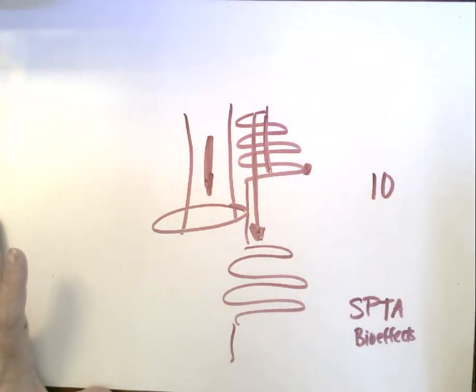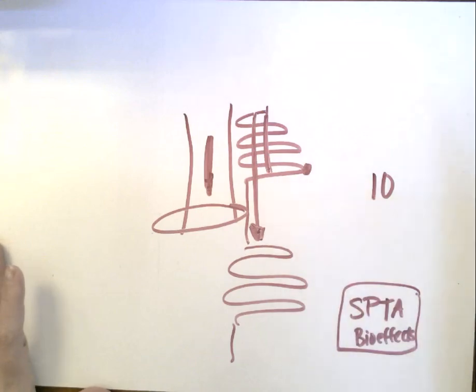There are considerations to take in when we're just looking at the pulse average, like just the on time of the pulse. It all plays into bioeffects in general, but our big one is SPTA. I don't know that I have a much better answer for you than that there are multiple ways to consider it. They measure them all just to make sure that we are staying within a safe range of ultrasound energy for our patients.